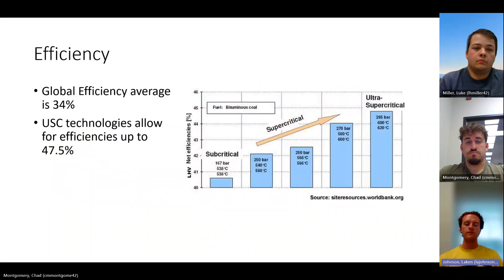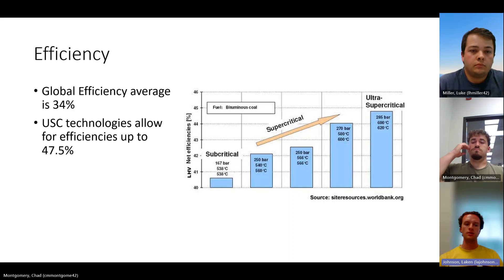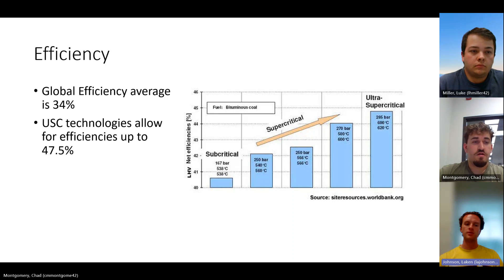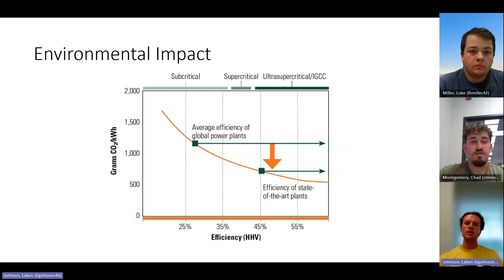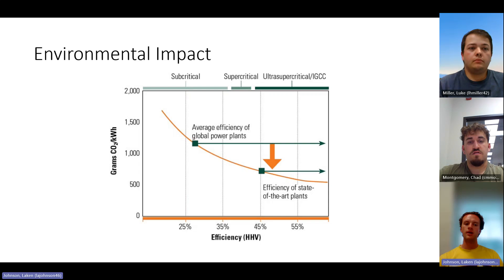This graph illustrates the efficiencies from subcritical up through ultra supercritical. The global average efficiency is about 34 percent, but you can hit the upper threshold of 47.5 percent with ultra supercritical plants. The second graph illustrates the environmental impact — as you move from subcritical to ultra supercritical, the increased efficiency directly reduces grams of CO2 per kilowatt hour.